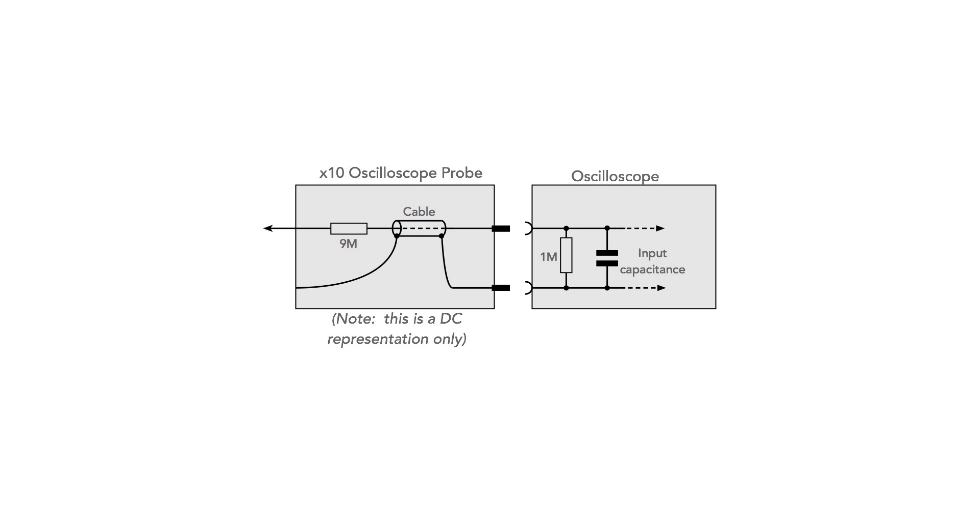For times ten probes, to compensate for the scope capacitance, a capacitor is placed across the nine megaohm resistor in the probe. Compensation adjustment is provided either at the remote end of the probe or where it connects to the scope. The adjustment enables the correct capacitance potential divider ratio to be obtained to take up any small changes in capacitance, and this gives a flat response.